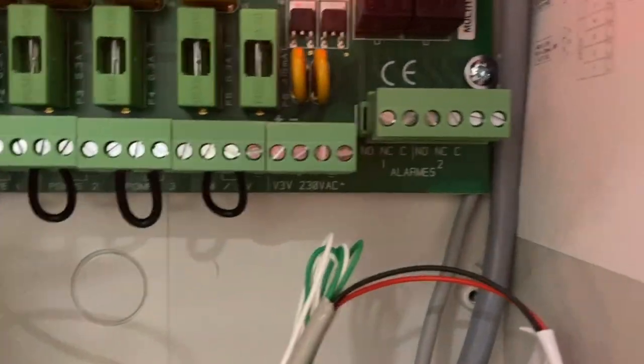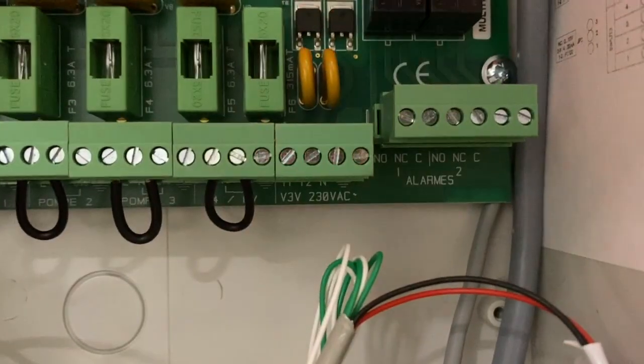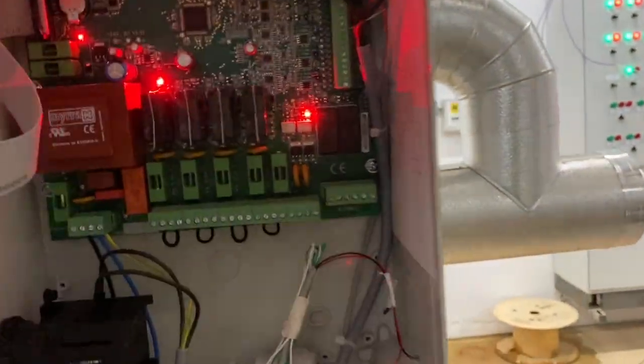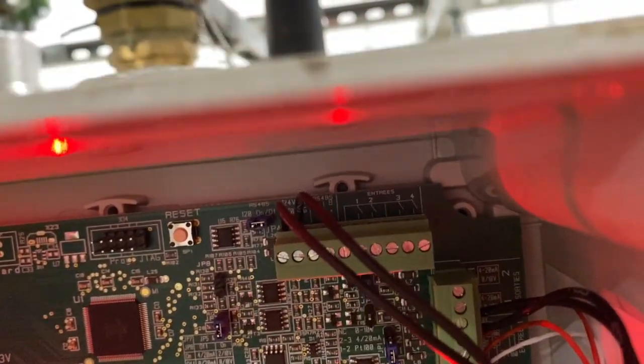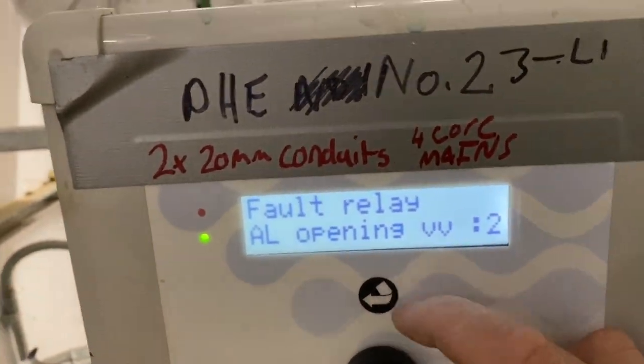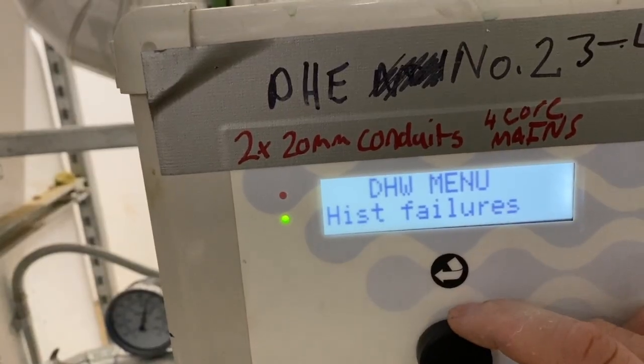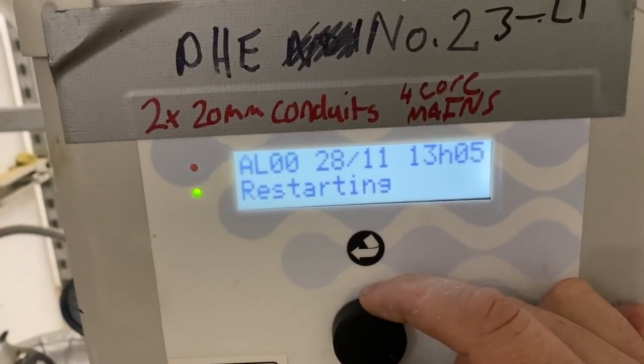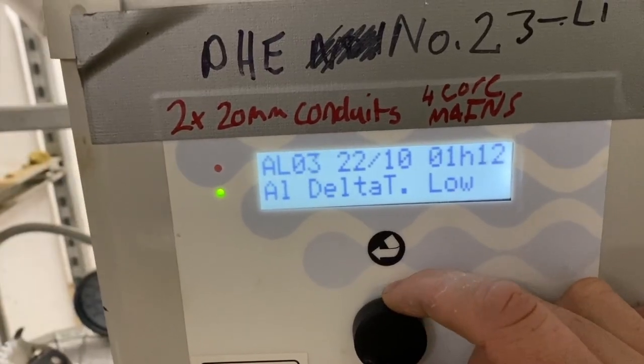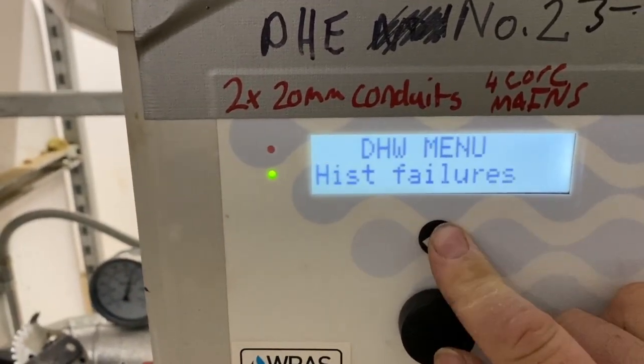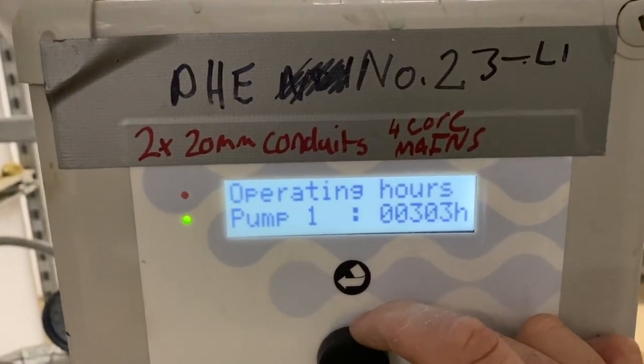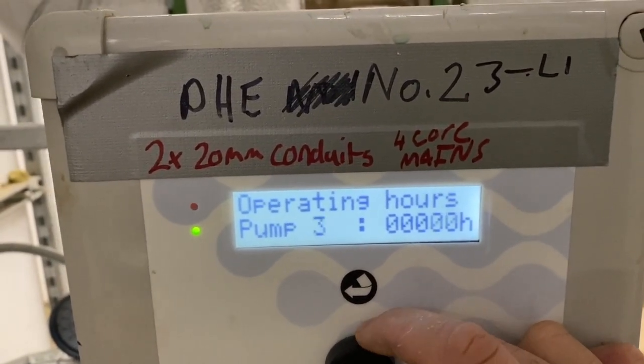In here, the bottom right is the alarm cables for the BMS, normally open, normally closed. In the right hand side there you'll see is the wiring diagram. Up the top here, if you can see towards the right, you've got a common and 4 in that top right corner, which is for the demand from the BMS. The wiring diagram is in the box. History of failures should be 0 anyway. Operating hours will just be pumps tested through the factory.